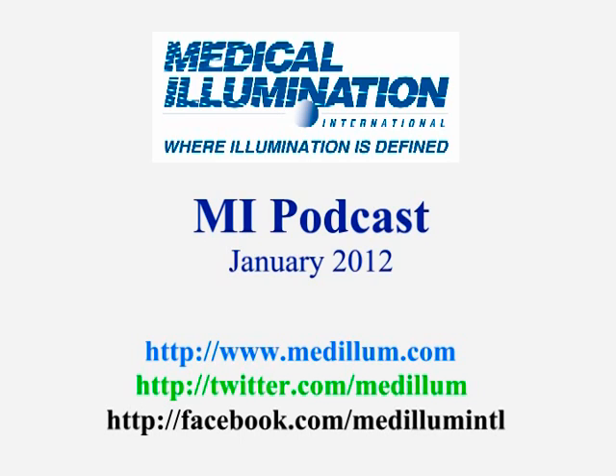With the electrician, you could ask them, by chance, do you have experience with installing medical lighting specifically, as opposed to just your standard room lighting? Yes, and that's an important qualification too. We talk about being able to be sure that the current mounting is sufficient. One of the things that you can do is download, like we mentioned, that pre-installation guideline that's on the website for your new product, and print it out, hand it to them, fax it to them, refer them to it from our website, and have them look at it.